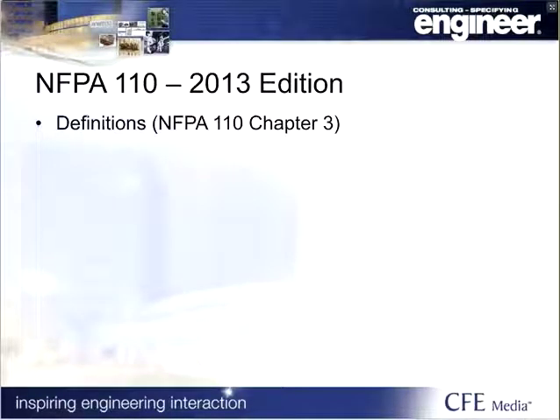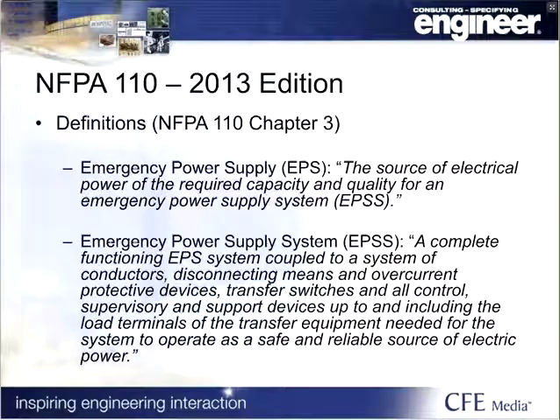NFPA 110 makes use of two important terms throughout the standard, EPS and EPSS. I have the definitions from NFPA 110 up on the screen for you to read. But the EPS is basically the generator or generators in parallel and includes up to the first disconnecting device. The EPSS includes the EPS and all distribution equipment and controls up to the load or output terminals of the transfer switches.